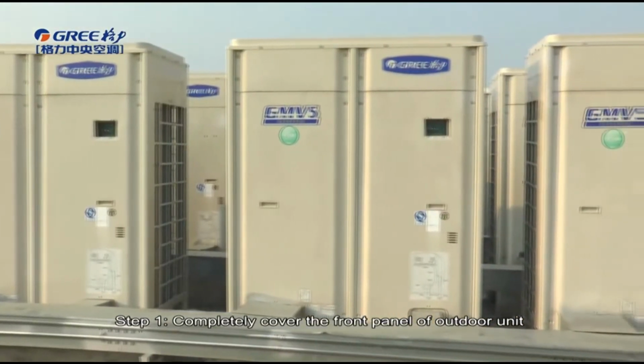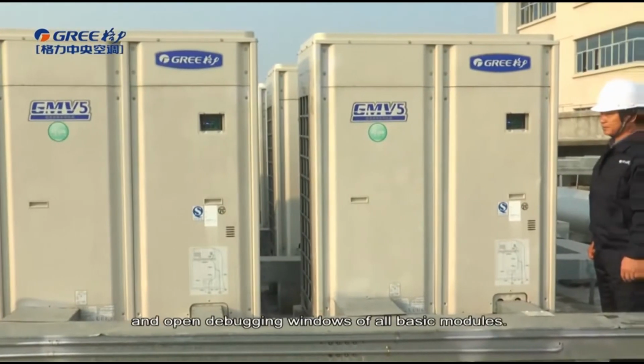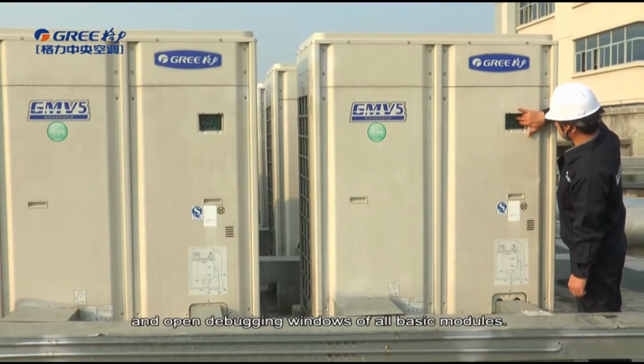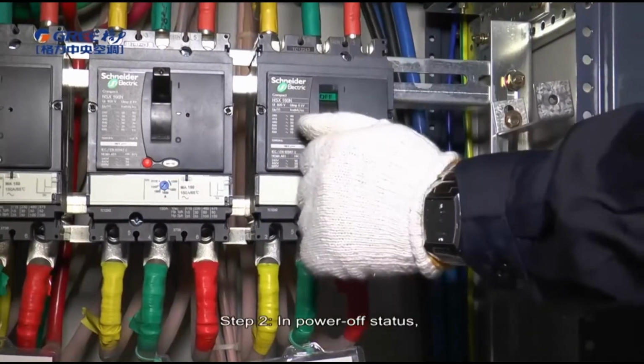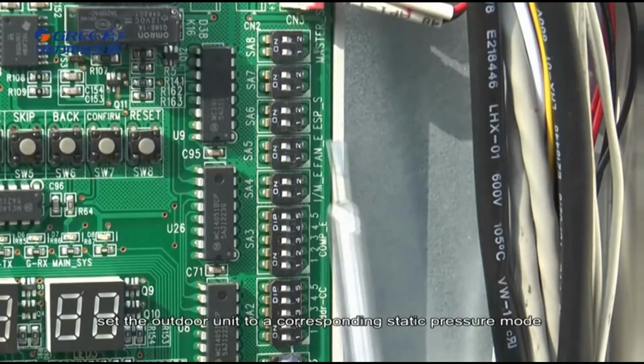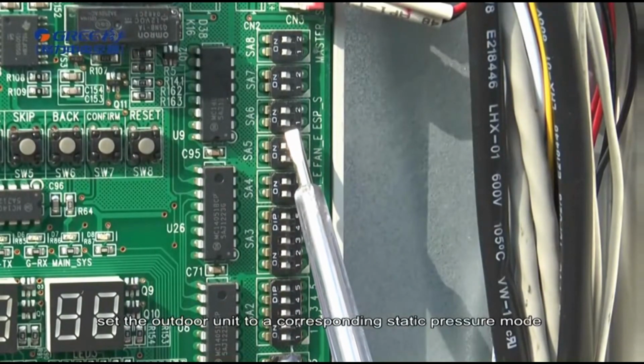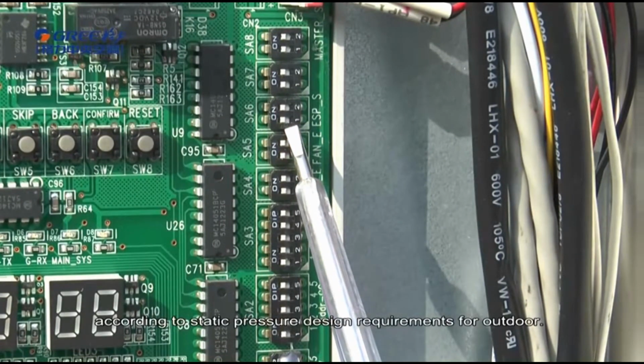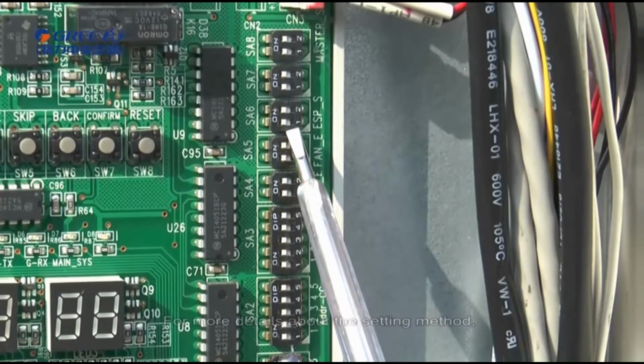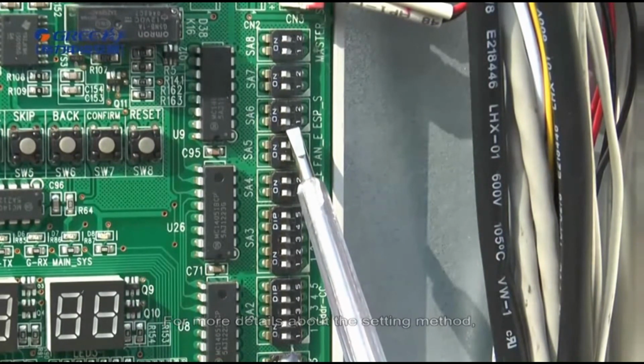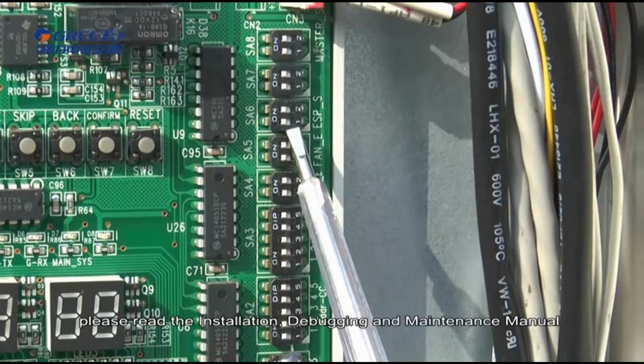Debugging through the main board buttons. Completely cover the front panel of the outdoor unit and open debugging windows of all basic modules. In power off status, set the outdoor unit to a corresponding static pressure mode according to the static pressure design requirements for outdoor. For more details about the setting method, please read the installation, debugging, and maintenance manual. If there are no static pressure requirements, keep the factory settings.